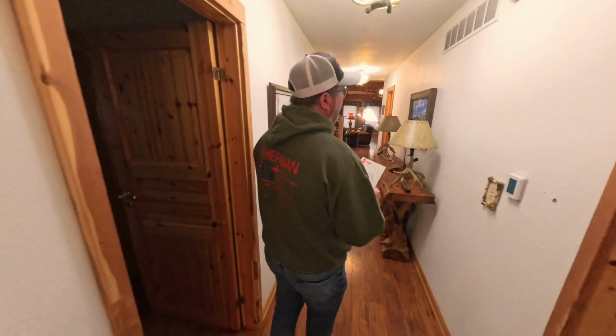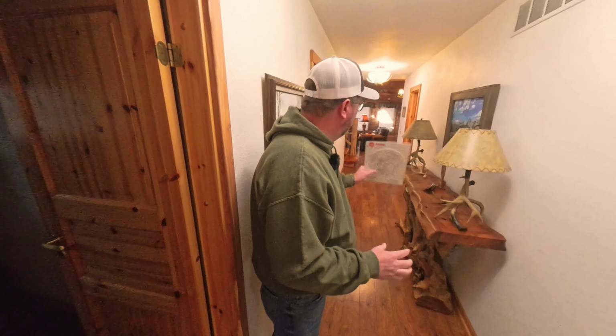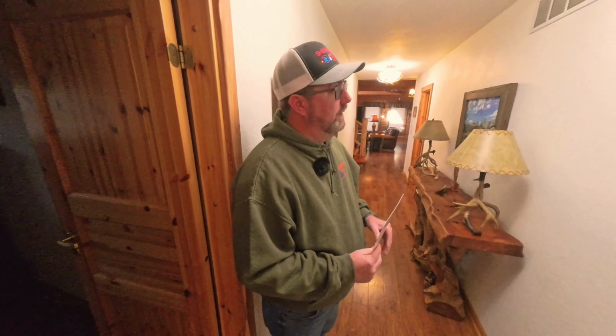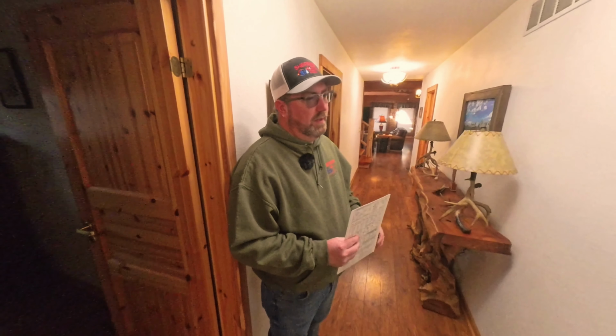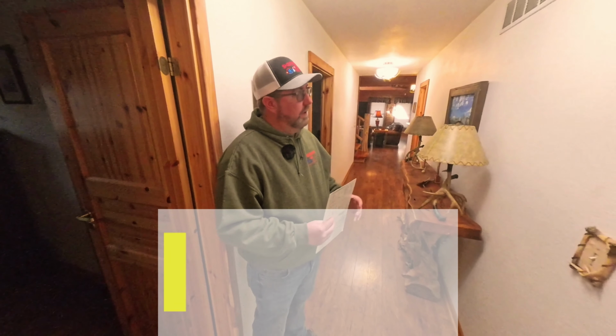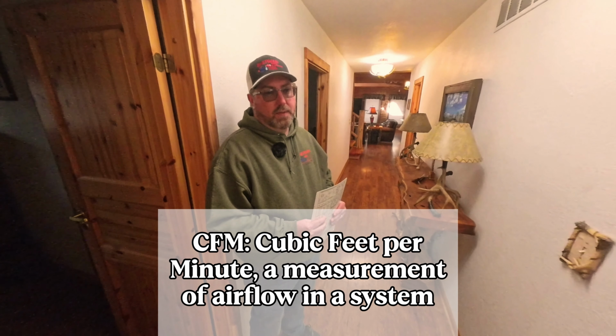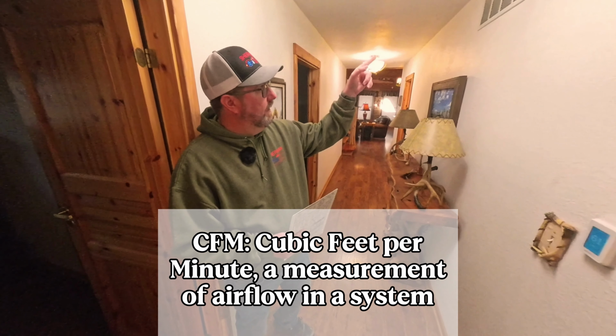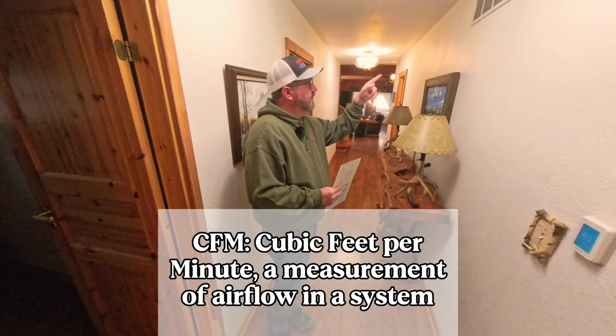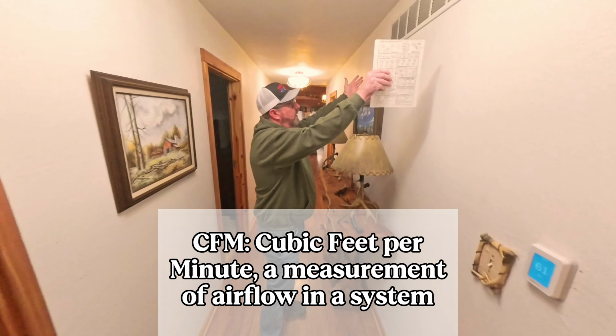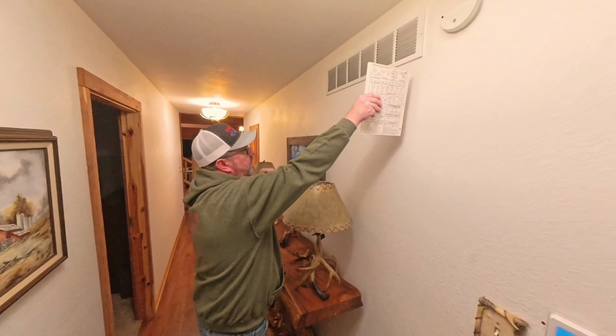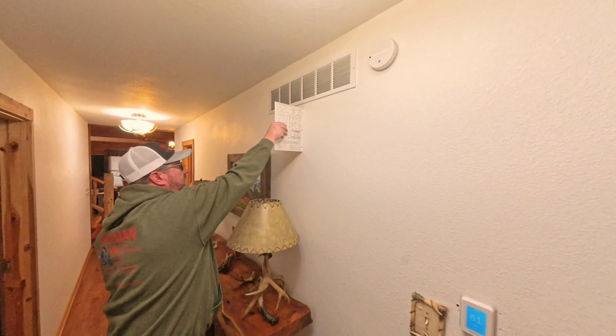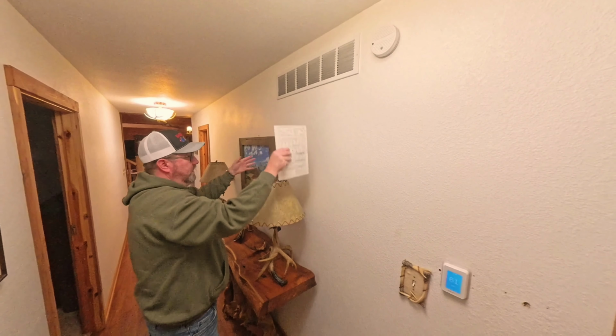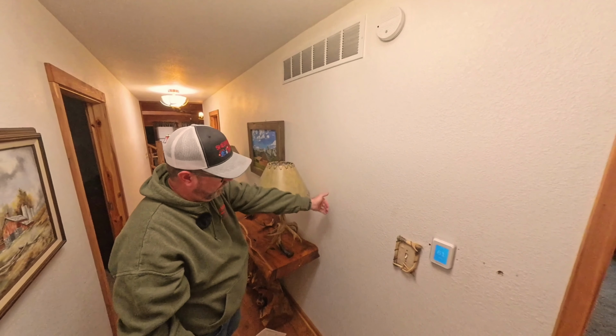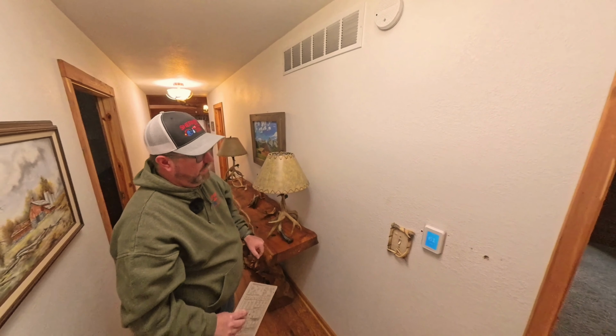Some of the things we looked at with the homeowner, he was having some uneven airflow and some uneven temperatures throughout the house. We started by looking at the size of the equipment and trying to figure out how much CFM the system would need for return and supply. And when we look at these return air grills, this is what we call a 30-inch wide return air grill. So in other words, it has 2 stud spaces worth inside this wall that it used as ducting, drawing down through that wall into the basement.